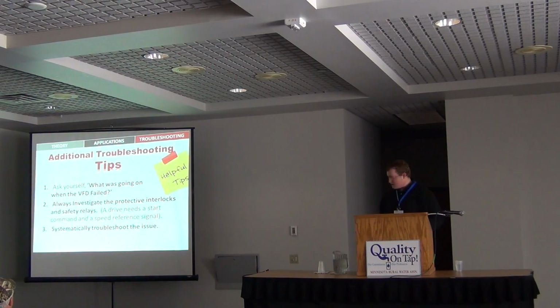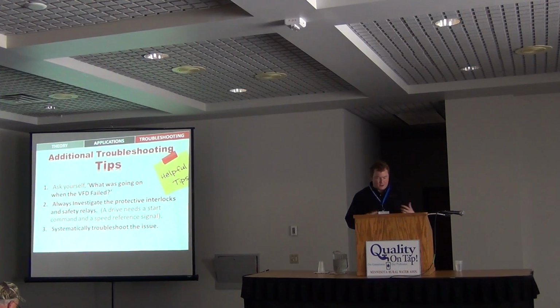a few more tips is just make sure you know what happened when you had a problem and document that. So if you need to call someone, you can explain to them what was going on when the problem failed. That helps consultants and suppliers a lot. If you say, well, the power went out and then the generator kicked on, and when the generator kicked on, the VFD didn't restart. Okay, well maybe it's a setting in the VFD or something like that that can be changed.